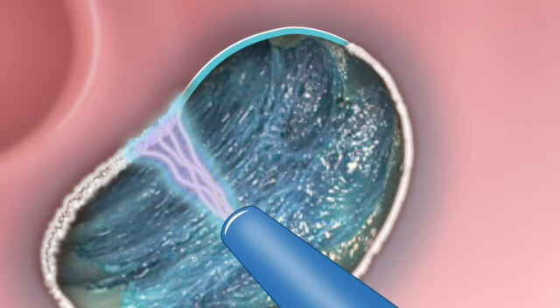Right. But when that high-voltage current hits the gas stream right as it exits the tip of the catheter, this massive physical transformation occurs. It ionizes the gas, right? Exactly. The electrical current is so intense that it literally strips the electrons away from the outer shells of the argon atoms. Wow. And that process of ionization converts that stream of inert gas into a plasma. And plasma is conductive. Highly conductive. It becomes the medium for the electricity. So the current uses that stream of plasma to jump from the metal tip of the catheter across that 1 or 2 millimeter physical gap directly into the targeted tissue. So that's the non-contact mechanism.